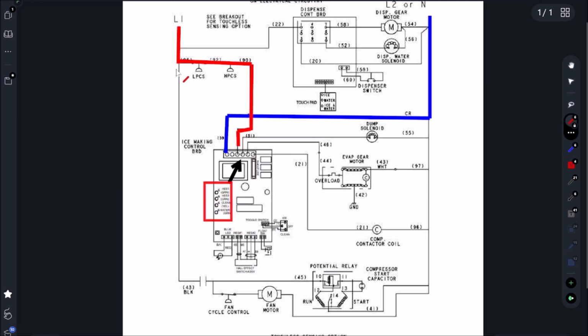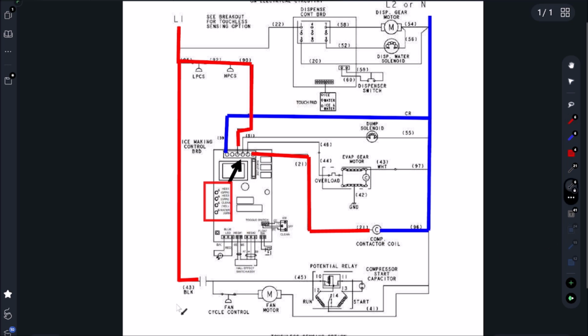The second thing I tested was we came down here and we came to our contactor. What closes the contacts on 43? Let's go to our contactor coil, and it's power here from the board. And then our neutral side is again a straight shot to our neutral terminal. So now the next thing you could do is test this contactor contact. But because we have that 15-minute delay, we literally have less than 1 minute to troubleshoot this.